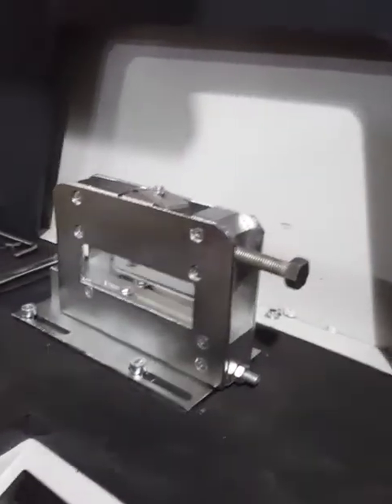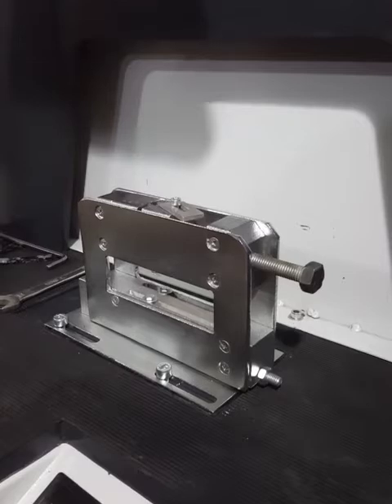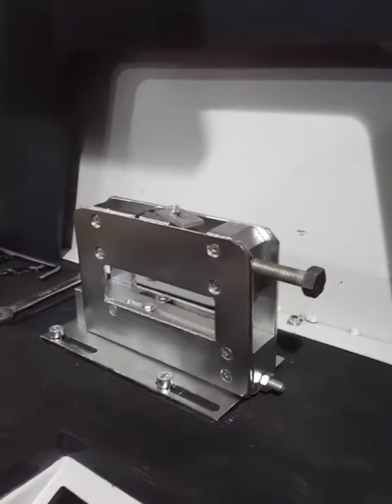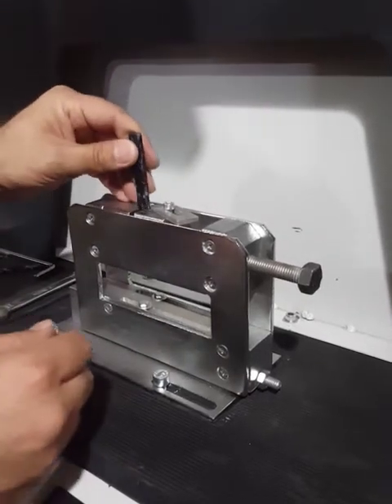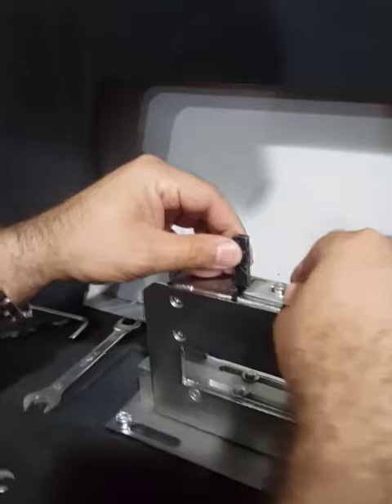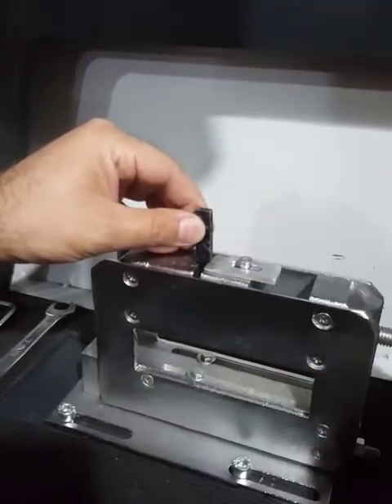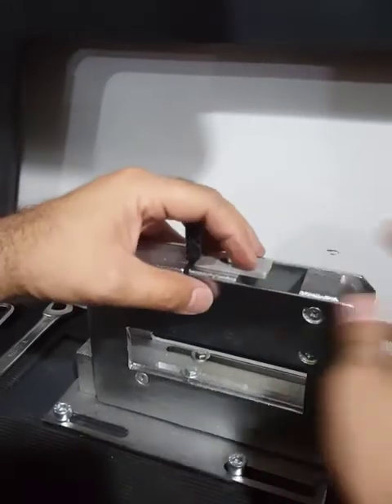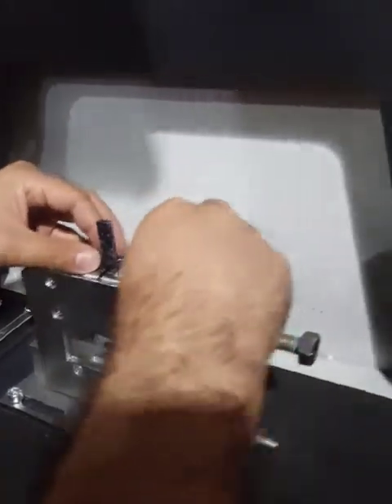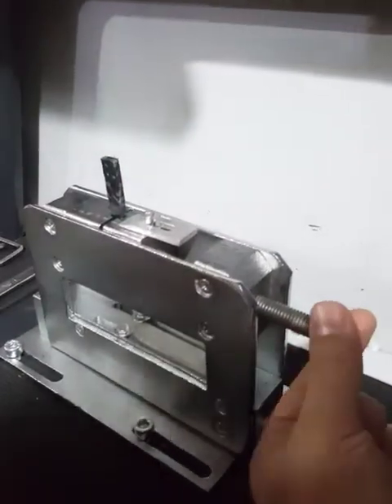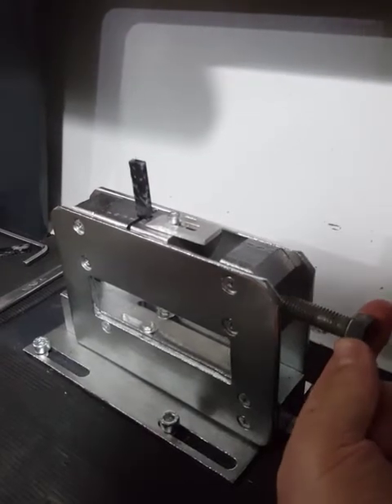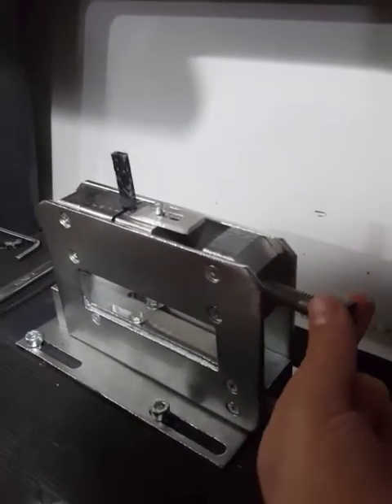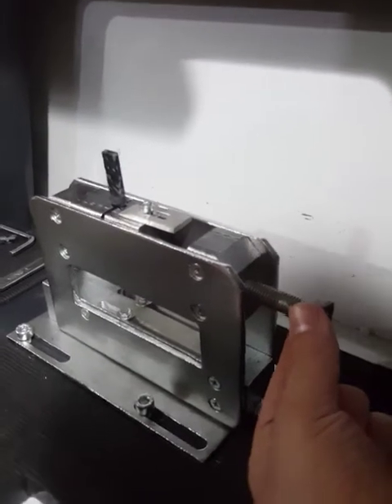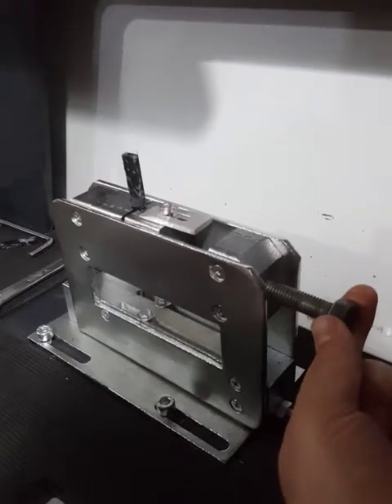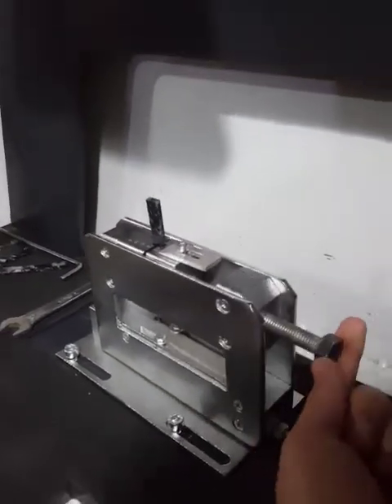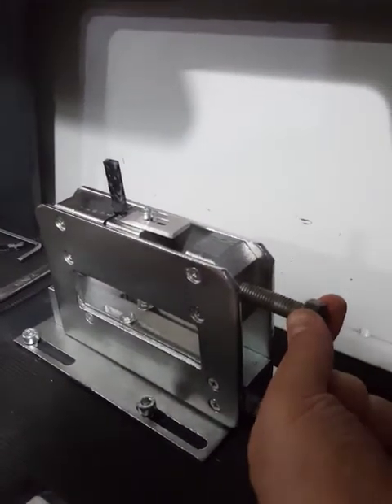After the height of the gripper is adjusted, as I showed, we need to adjust the left and right position of the gripper. Just put the sample in the gripper like this. You have a fixture just fixing the middle point of the sample. Then tighten this screw. It should be manually tightened, so as not to tighten it more than is needed. This is a screw, and you need to tighten it manually. Don't use any kind of wrench or any other tool. That's enough to fix it, to tighten it by hand.